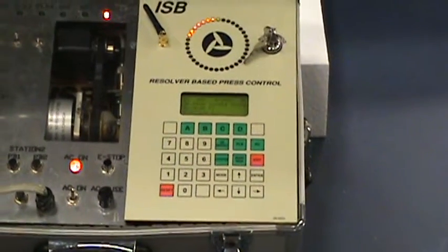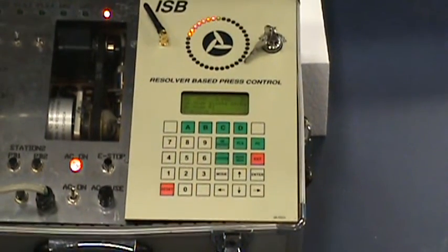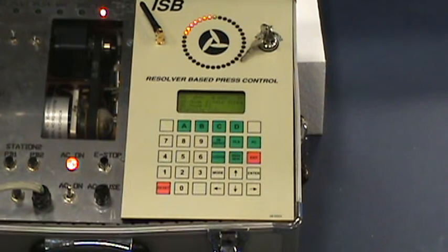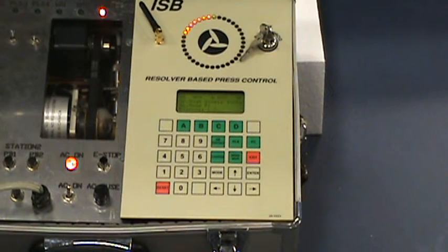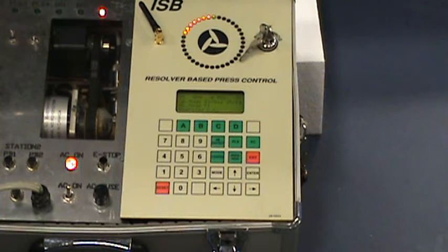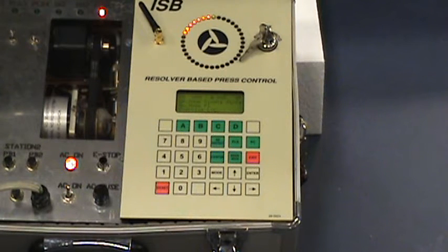I'd like for these guys to know that they've got to look down in that crack. There's a cutout on the sheet metal and there's a surface mount LED on the inside. It's pretty bright, you can see it. Your wires might be covering some of them, but you'll be able to use it as a continuity checker. When the input's turned on, it's going to light up red. And when the input's turned off, it's going to be off. So that's the first thing to keep in mind.